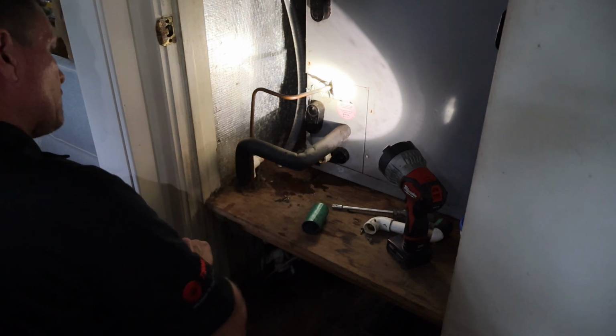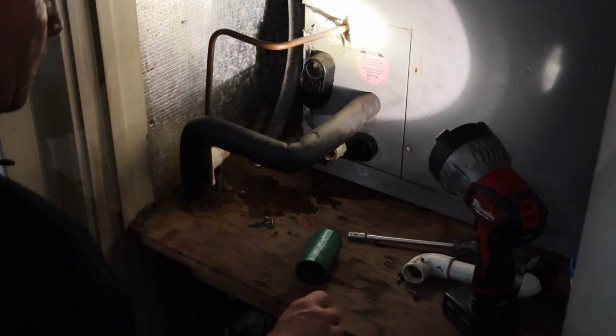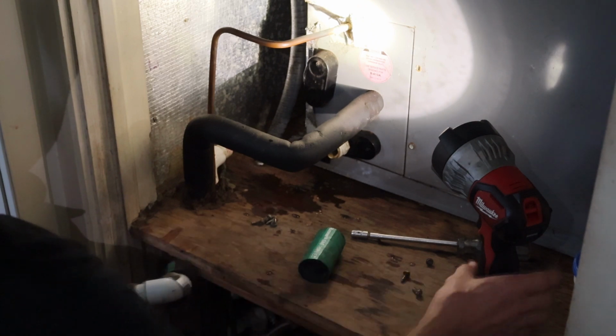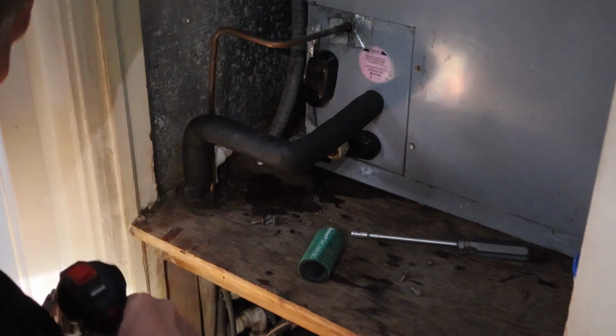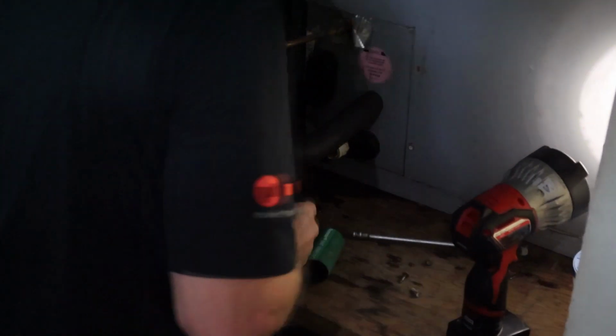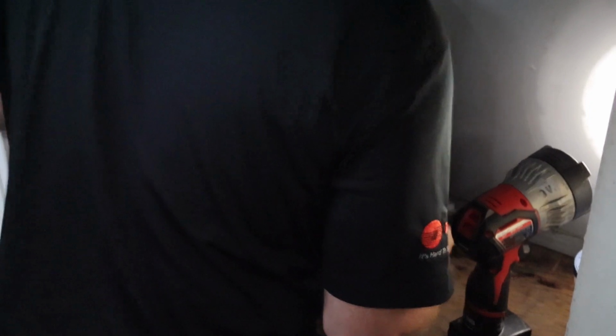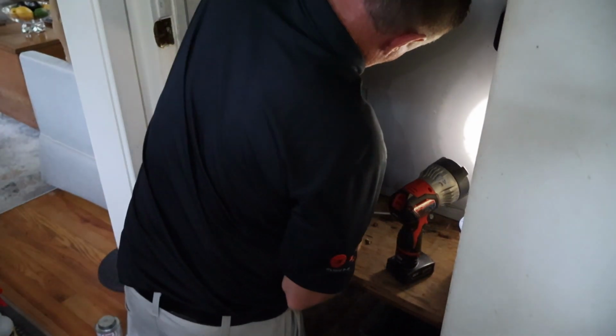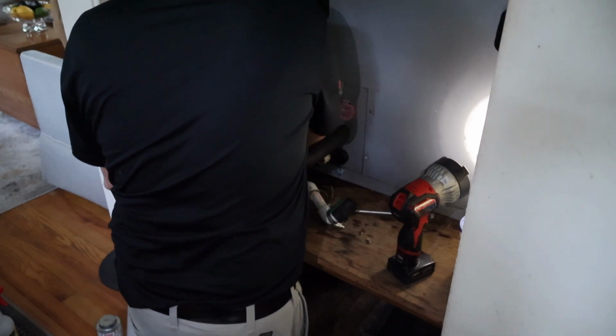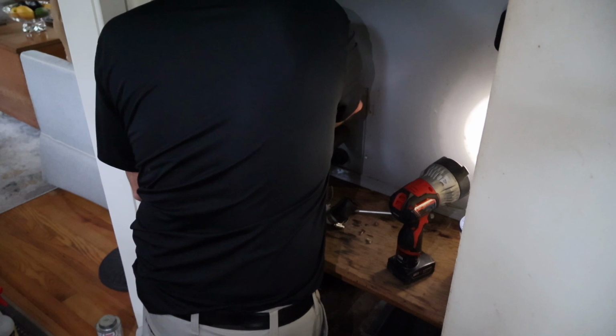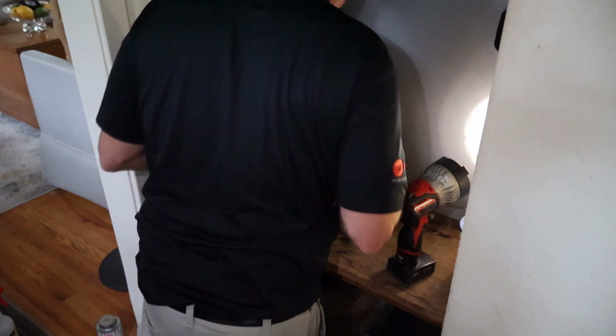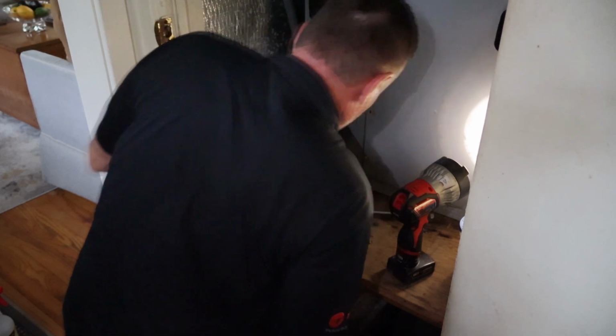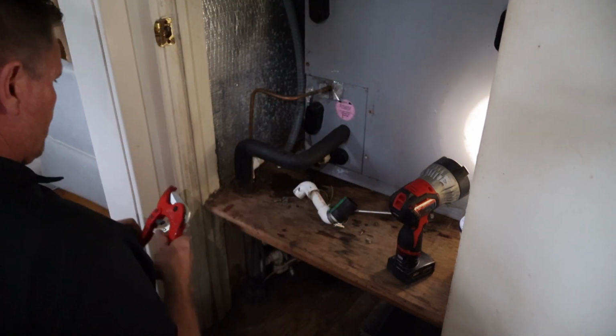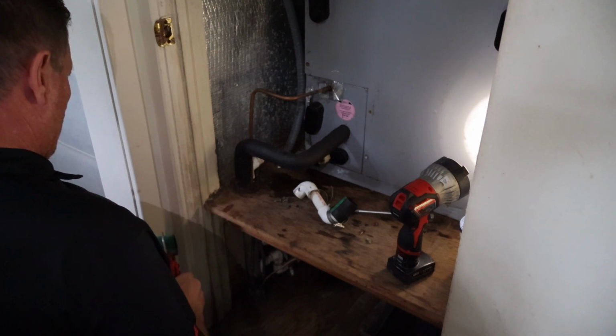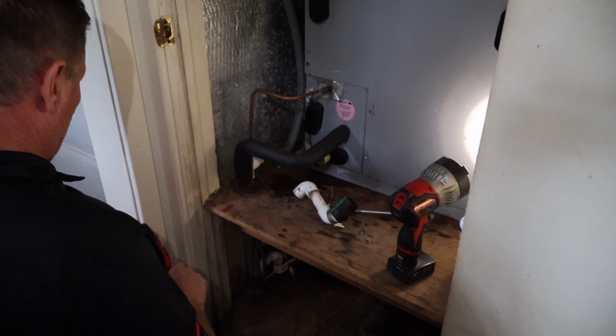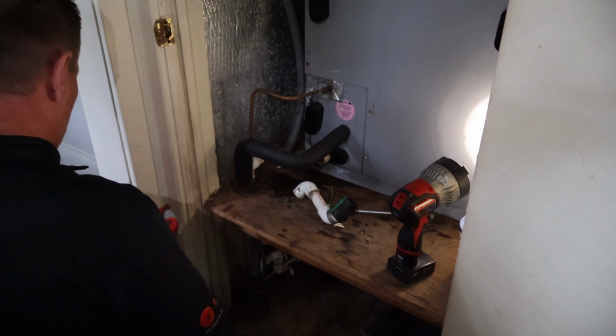We'll move on from that shortly and move up to the blower compartment, also checking the coil for cleanliness. What we typically look for in the blower compartment is a buildup on the blower wheel, dust or any mold or whatnot, something that warrants a problem and means it may need to be removed and cleaned. Most of the time it's pretty moderate and doesn't really warrant the cleaning process. If it does, technicians typically let the customer know that it may have to return. Typically we don't allot enough time to clean a blower wheel, so we may have to return and pull it and clean it, as well as the coil if it's dirty too. So we'll be to that point shortly.